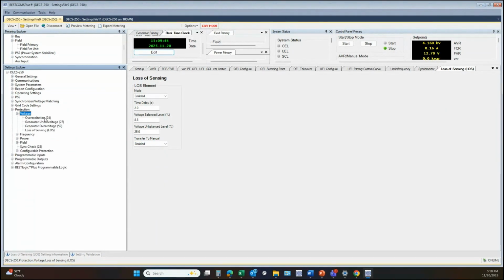We do have other over and under voltage protection elements, under and over frequency elements, and power elements that can be set up. Again, most of the real protection is handled by a generator protection relay to perform the tripping of the machine, but these can be set up for annunciation.